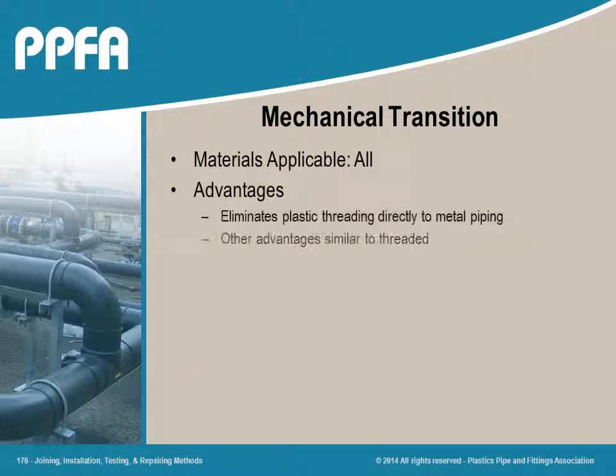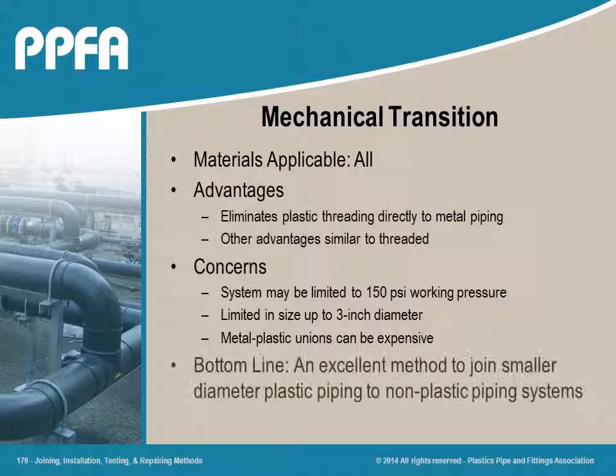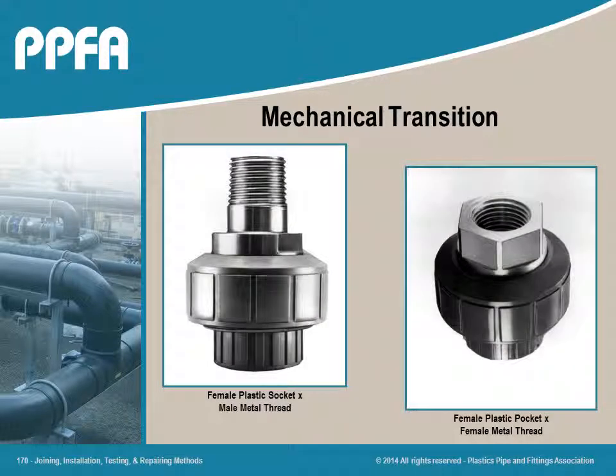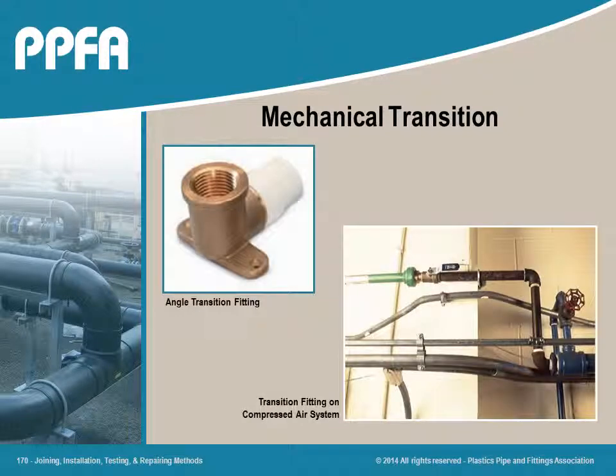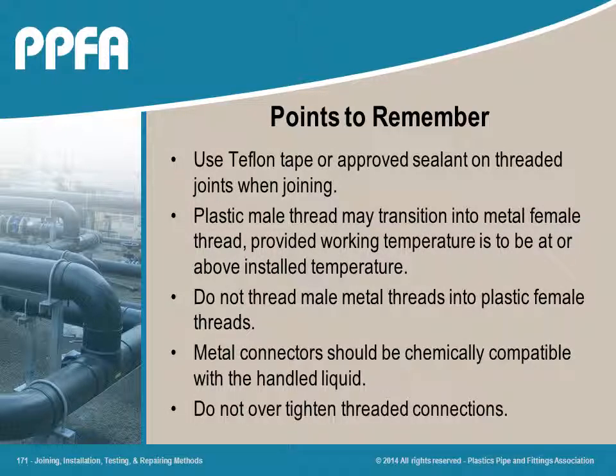If you must use a threaded system in thermoplastics, the use of transition fittings should be considered. These fittings allow thermoplastics to be joined with metal piping systems, minimizing many engineering design concerns that might occur when directly threading plastic piping to metal connections. The additional cost of using transition fittings more than offsets the possible lack of joint integrity with the direct threaded pipe. The two limitations of this system are a maximum 150 psi working pressure and sizes up to 3-inch diameter.